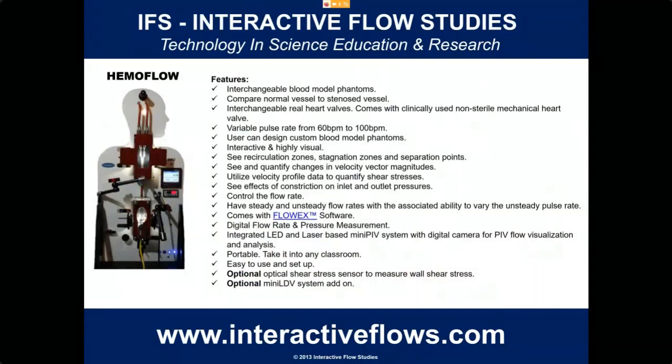Finally, the HEMOFlow system. The HEMOFlow system is the most sophisticated system we have. It has pulsing flow to simulate heart flow. It's designed for biomedical engineers specifically. It has interchangeable blood model phantoms. It compares, for example, a normal vessel to a stenosed vessel.